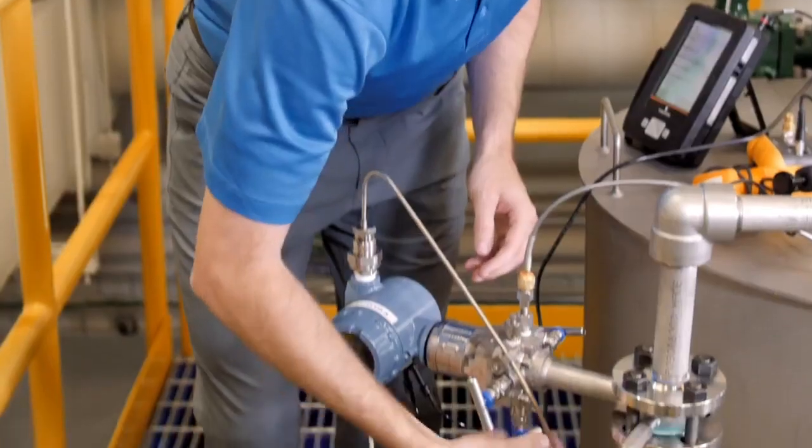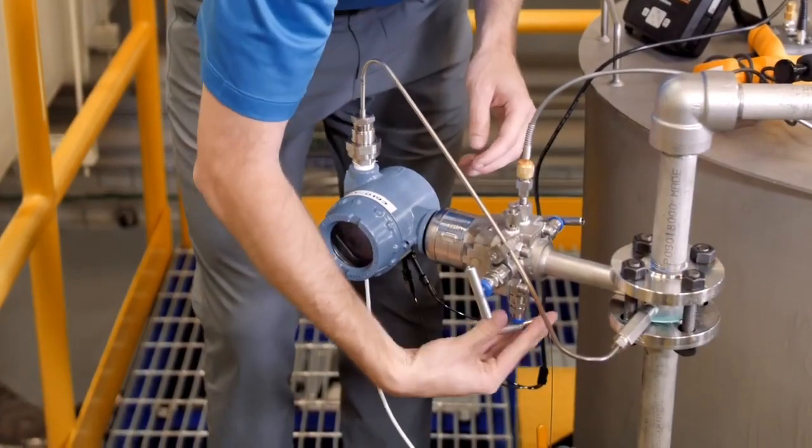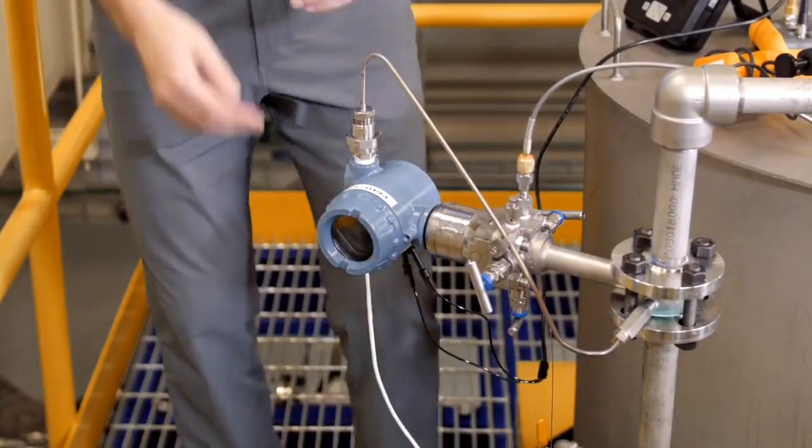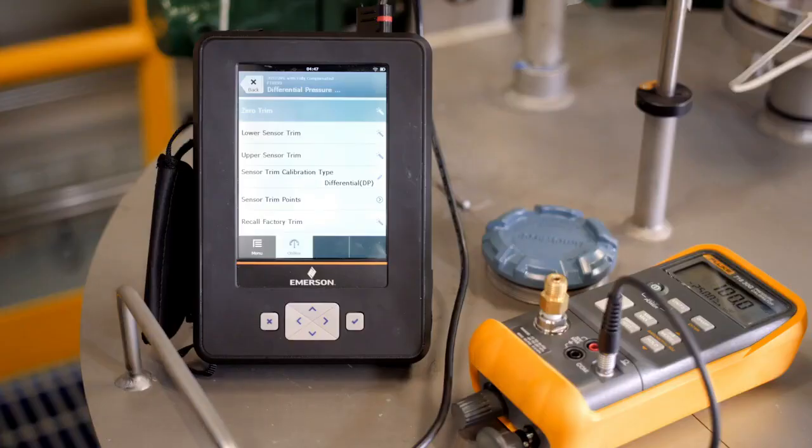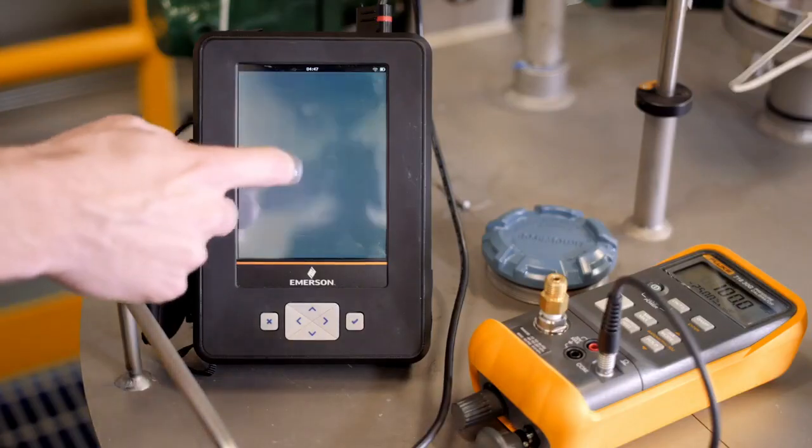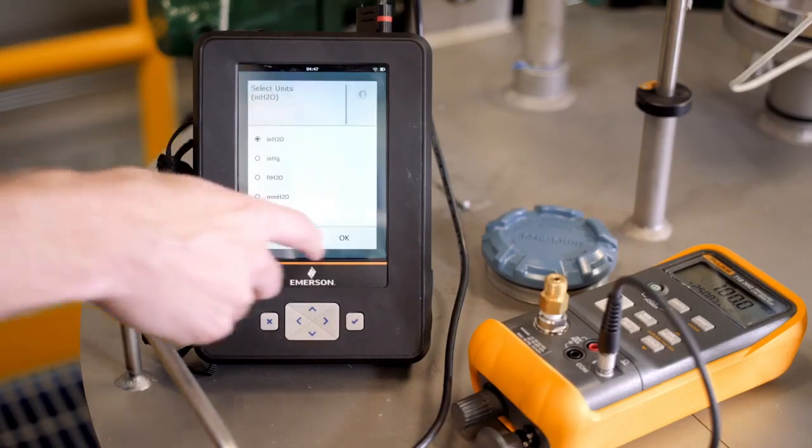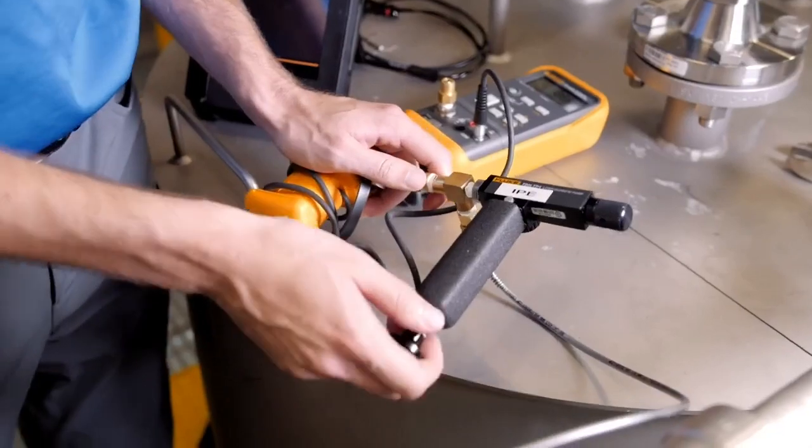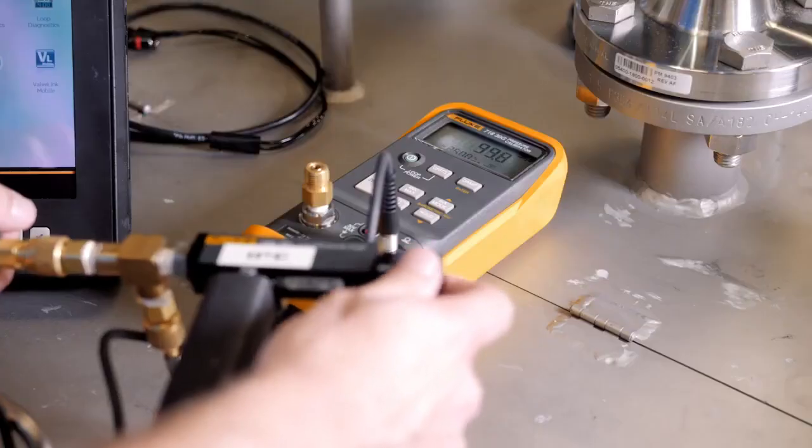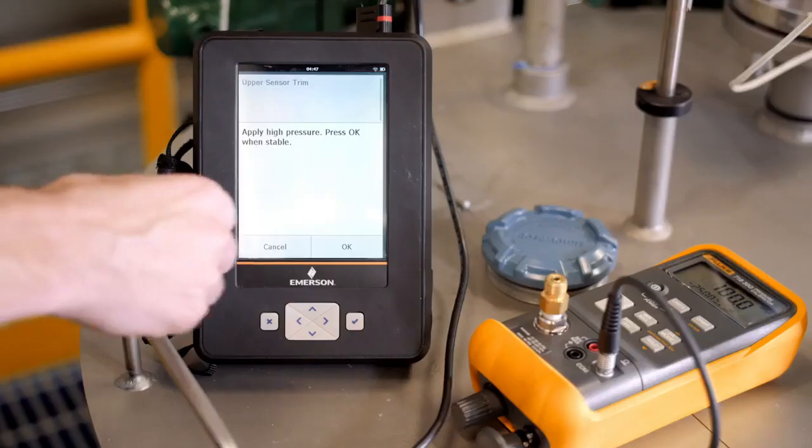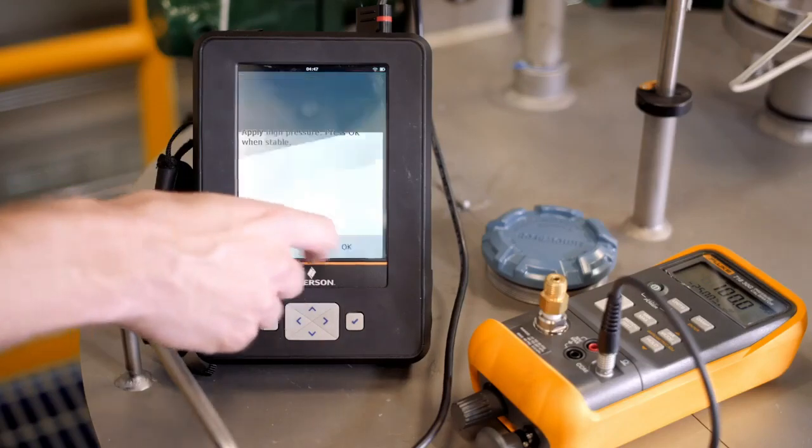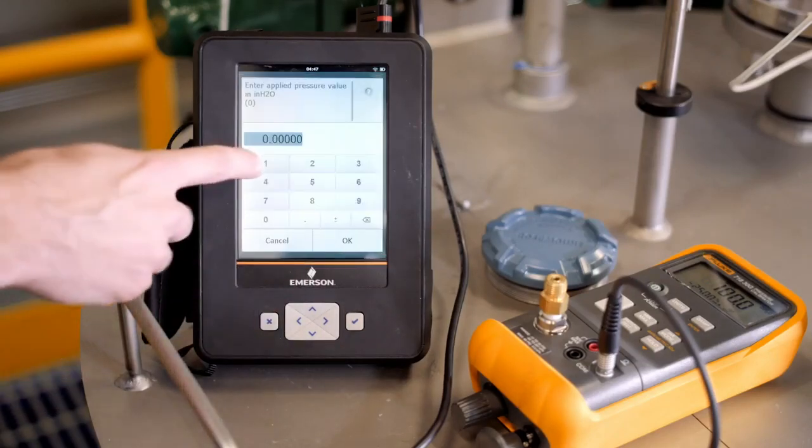The next step is to perform an upper sensor trim, which should be calibrated to the transmitter's upper operating limit. The valve should also be manipulated so that the high side is connected to a pressure source. Now select upper sensor trim. The first thing to choose is the units, and then we'll apply pressure to the transmitter. For this example, we'll apply 100 inches of water. Now enter that applied pressure on the Trex and follow the guided wizard to completion.